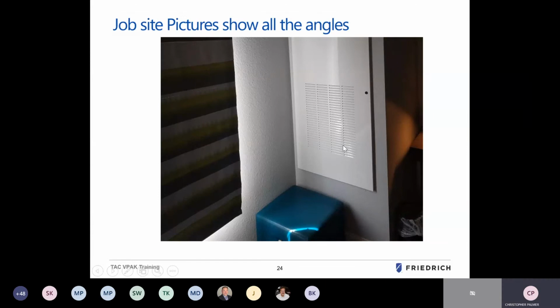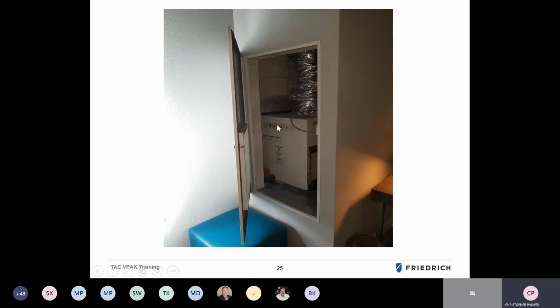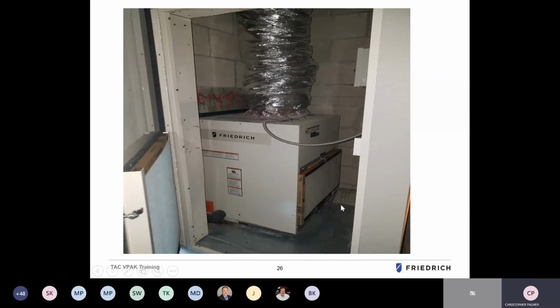This is another project showing a nice access panel, full closet, nice platform, block wall construction. In this image, you can see the contractor put sheet metal flooring on the platform so that you can disconnect the drain line and slide the unit around inside this closet opening, or get it to the edge to a mechanical cart or out for service. You can see the concrete block, nice sealed closet, nice clean straight duct connection, and a disconnect box on the right-hand side for your proper power supply disconnect.